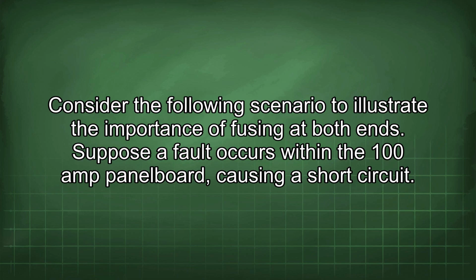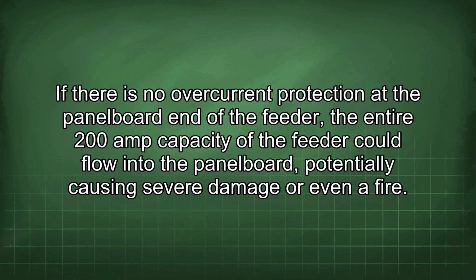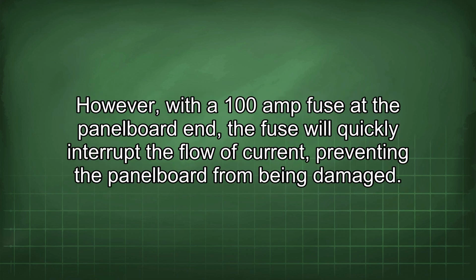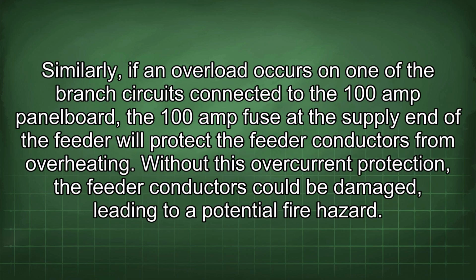Consider the following scenario to illustrate the importance of fusing at both ends. Suppose a fault occurs within the 100 amp panel board, causing a short circuit. If there is no overcurrent protection at the panel board end of the feeder, the entire 200 amp capacity of the feeder could flow into the panel board, potentially causing severe damage or even a fire. However, with a 100 amp fuse at the panel board end, the fuse will quickly interrupt the flow of current, preventing the panel board from being damaged. Similarly, if an overload occurs on one of the branch circuits connected to the 100 amp panel board, the 100 amp fuse at the supply end of the feeder will protect the feeder conductors from overheating. Without this overcurrent protection, the feeder conductors could be damaged, leading to a potential fire hazard.